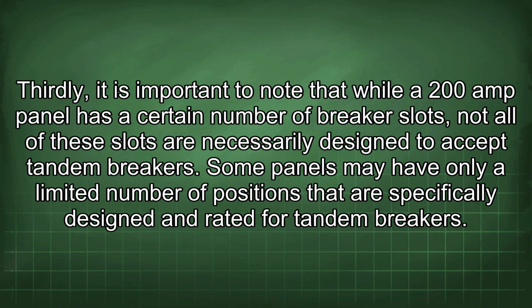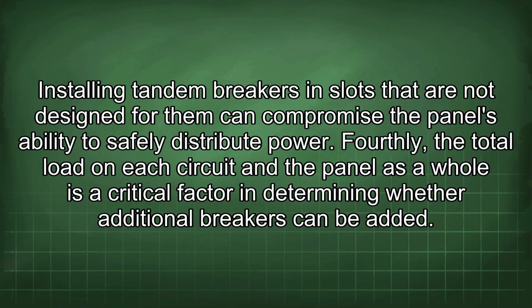Thirdly, it is important to note that while a 200 amp panel has a certain number of breaker slots, not all of these slots are necessarily designed to accept tandem breakers. Some panels may have only a limited number of positions that are specifically designed and rated for tandem breakers. Installing tandem breakers in slots that are not designed for them can compromise the panel's ability to safely distribute power. Fourthly, the total load on each circuit and the panel as a whole is a critical factor in determining whether additional breakers can be added.